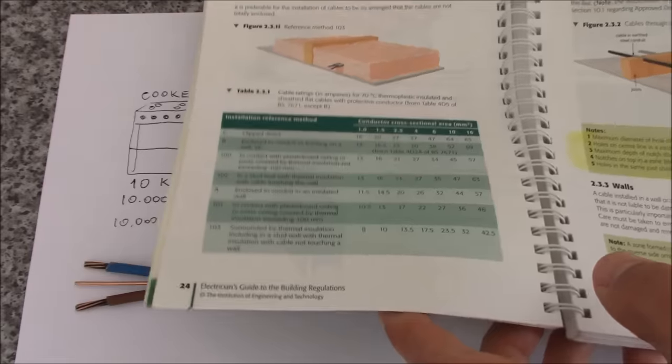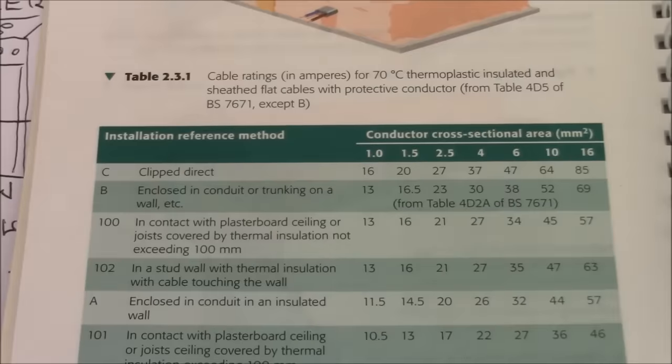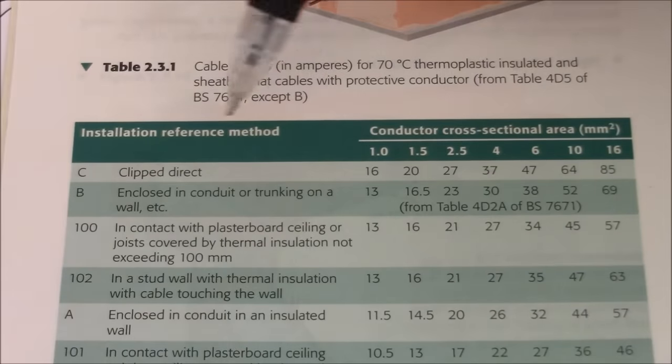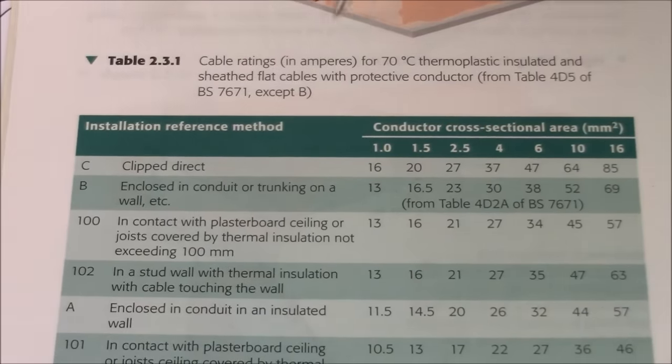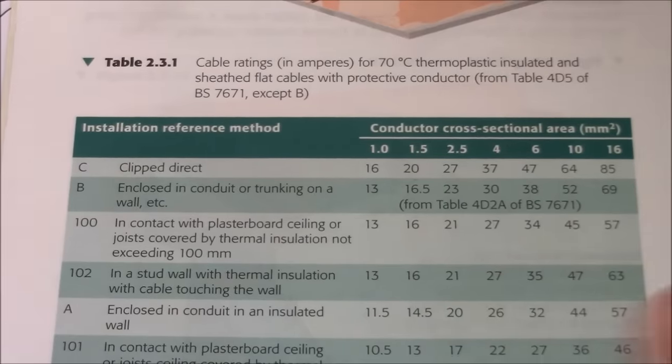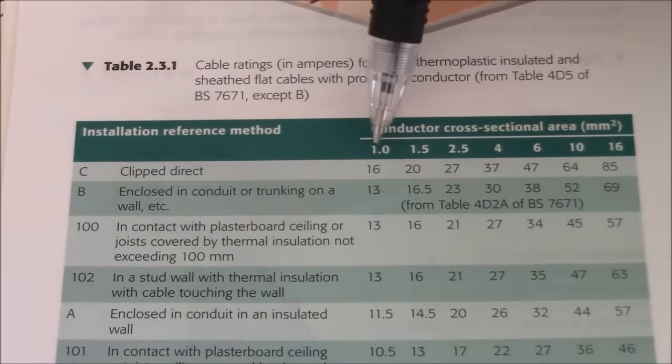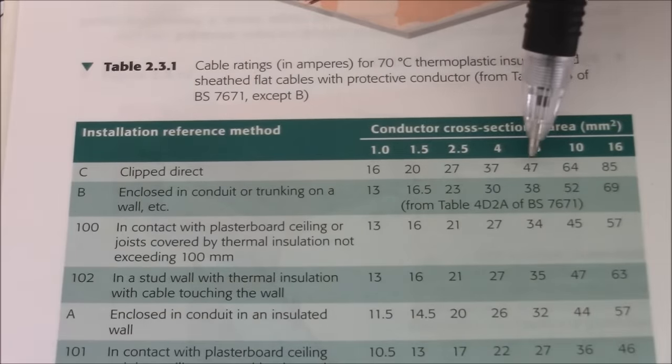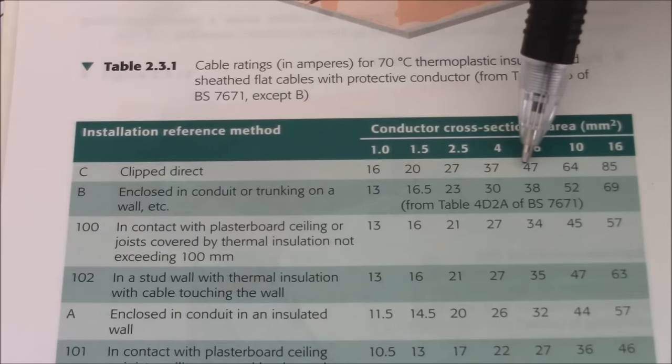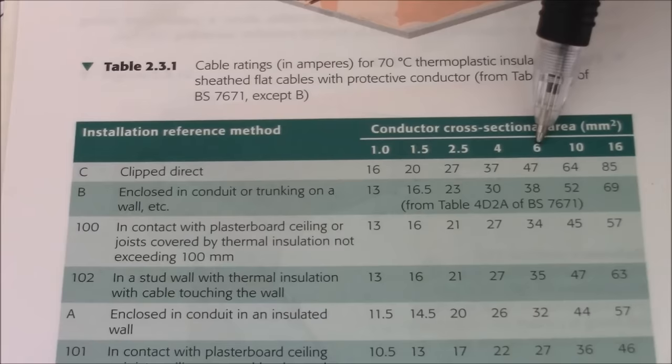So we know how we install it. Let's say we clip it direct to the wall. If we say that this has to be equal or bigger than 45 amps, let's have a look at the first column. 47 amps, bigger than 45. So that's the size of the cable, 6 mm.